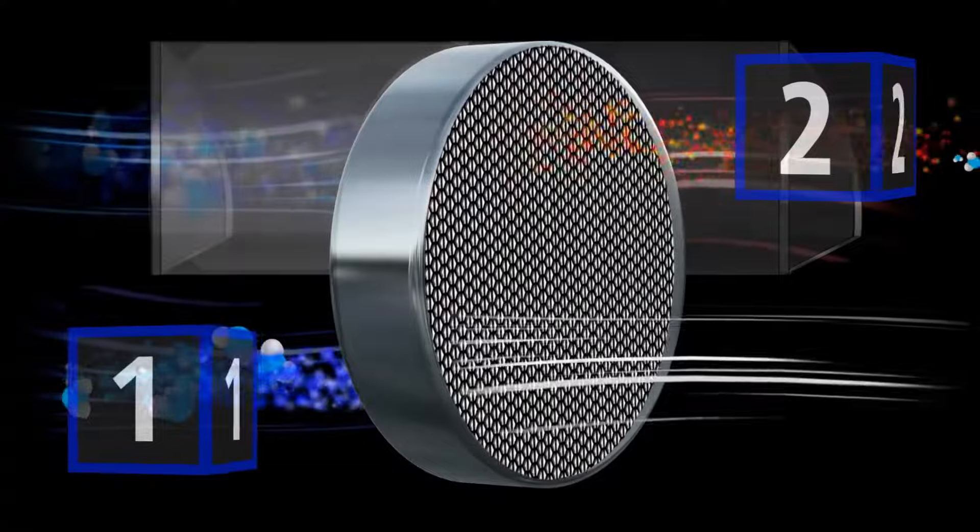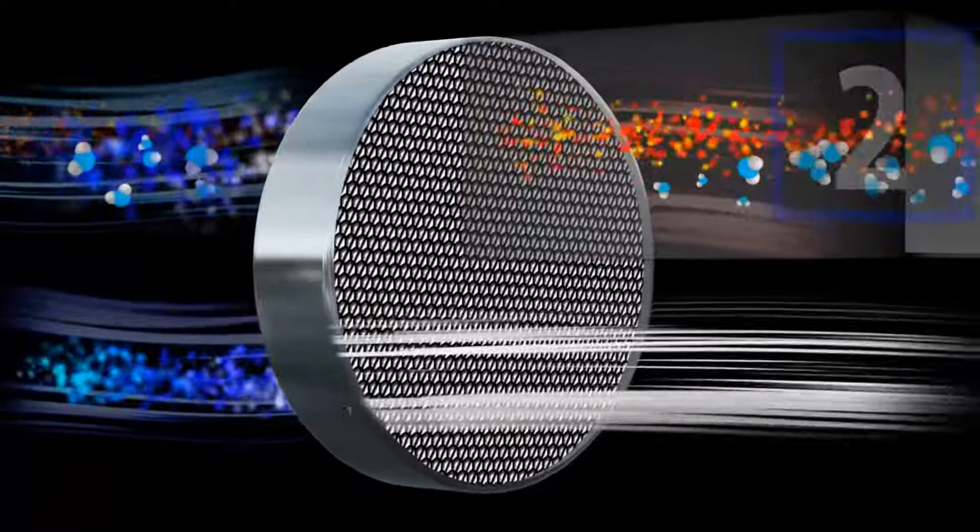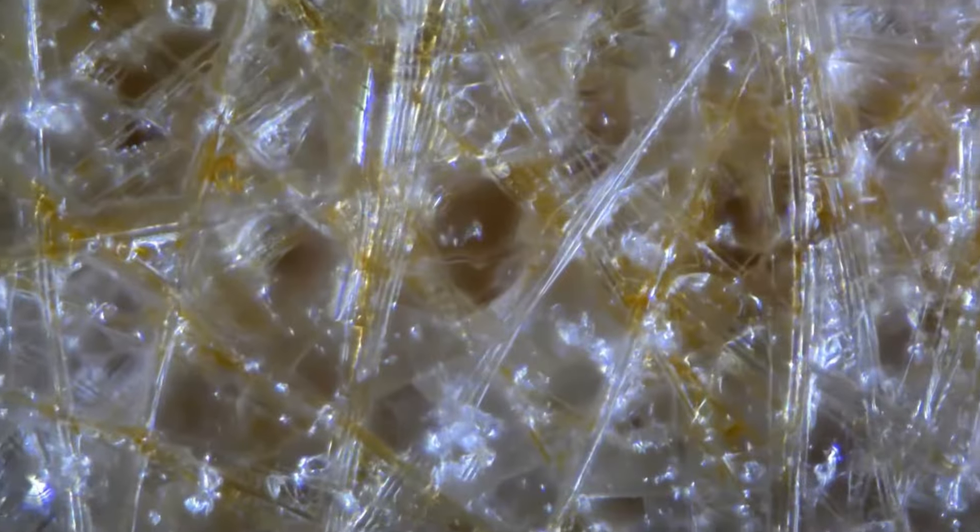This is called reactivation, or regeneration, of the desiccant. The heat we add to this airstream causes the bond between the moisture and the desiccant to be broken. The reactivation air, being heated, has a very low relative humidity, and therefore accepts that moisture that is being desorbed.